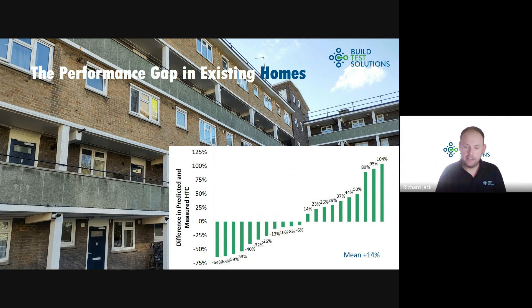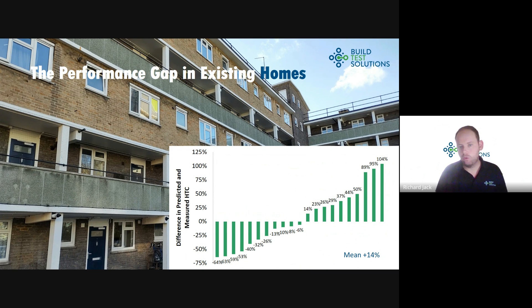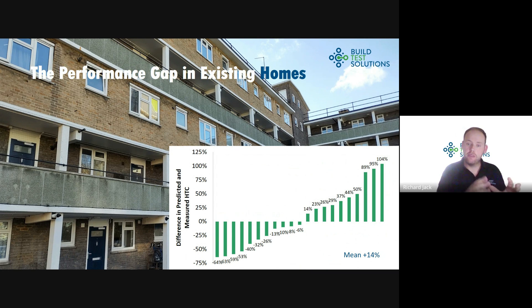So even within one building there is a real range of performance between flat types, and the measurement allowed us to identify some construction failures and think about how the building is really performing — what the best retrofit strategy would be. Any retrofit strategy here will have to deal with that thermal bridging issue.